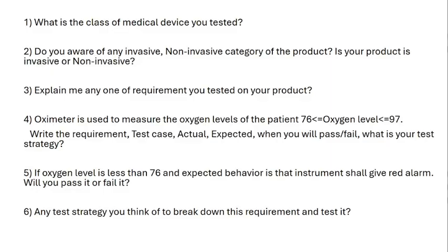And the second question is, are you aware of the invasive and non-invasive categories of products? Is your product invasive or non-invasive? So here we have to understand what invasive and non-invasive products are. Invasive means the device will be connected to the body through a skin cut or the device is used inside the body. Non-invasive means we won't use that instrument inside the body, so it is outside the body. My product, the electrosurgical generator, is a non-invasive product, and I said so.